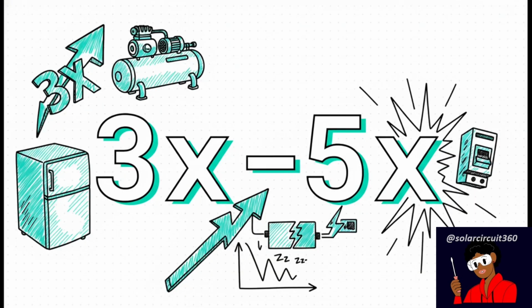And then we have startup surges. The initial power grab for things like air compressors, freezers, or well pumps can be literally 3 to 5 times higher than their normal running power. 3 to 5 times. This demands an instant, massive surge of current that can just completely collapse your voltage. Your inverter might be totally fine, completely capable of running the appliance once it's going, but it just can't handle that violent, split-second startup demand. So it triggers a low-voltage event before the appliance even gets a chance to spin up.